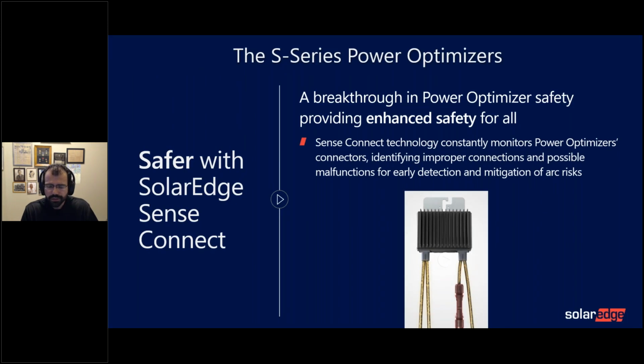Okay. On the optimizer side, SolarEdge launched last year a DC optimizer with patented and proprietary Sense Connect technology. This technology automatically detects and prevents potential electric arcs at the connector level rather than just the string level. With the ability to detect abnormal changes in connector temperature, Sense Connect constantly monitors power optimizer connectors, identifying improper connections and possible malfunctions. Once an abnormal temperature is detected, voltage is brought down to 1 volt, a safe voltage level. So in other words, this is designed to catch issues before they develop into potential fires, I mean electric arcs. This is why it is important to have Sense Connect, this technology that we have in the S series optimizers, which is already available to order from SolarEdge.